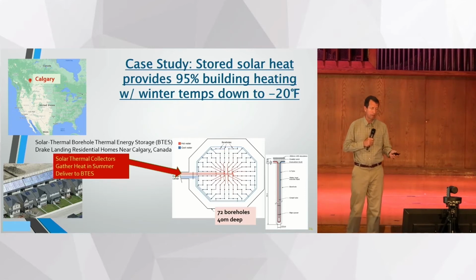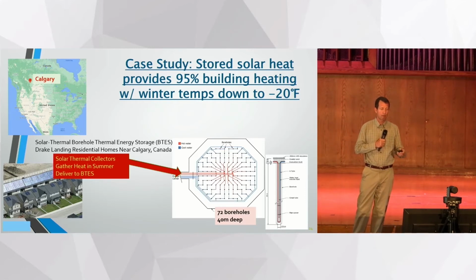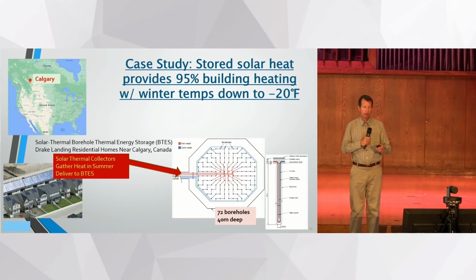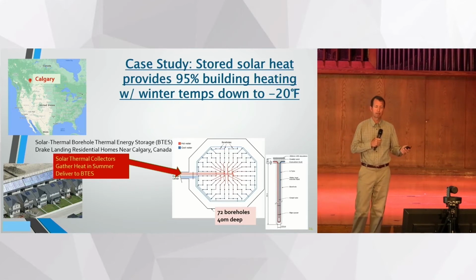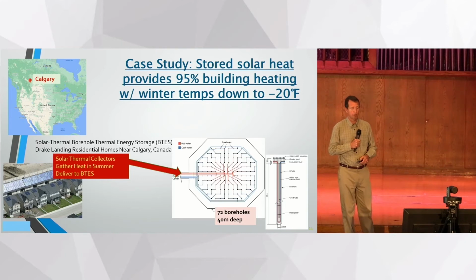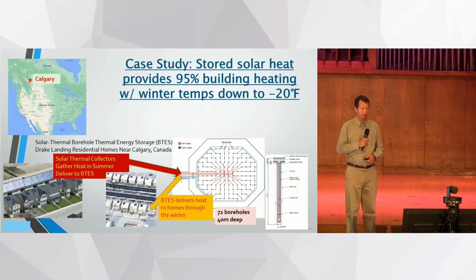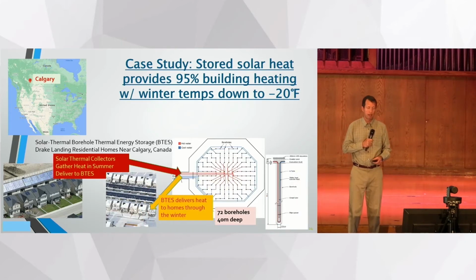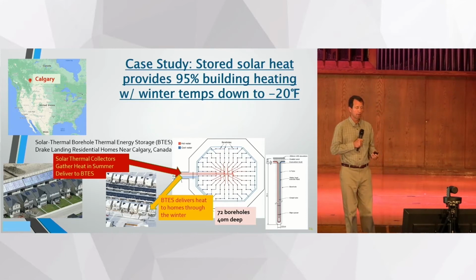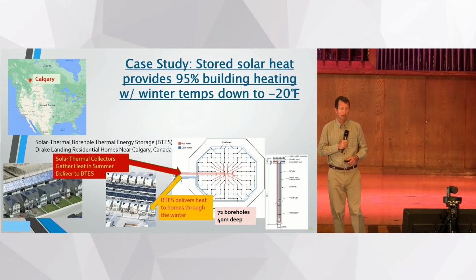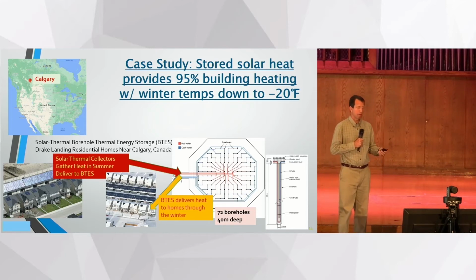So the water flows from the outside of the ring, outside of the BTES, to the solar collectors, and then back into the center. In the winter, we reverse that flow, and we flow from the outside into the center, where the water heats up, comes back to the buildings at about 150 degrees Fahrenheit, and directly heats the buildings with blowers.